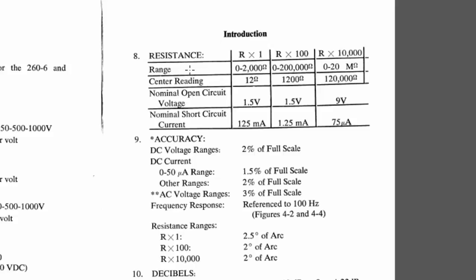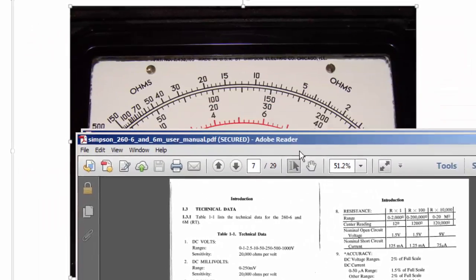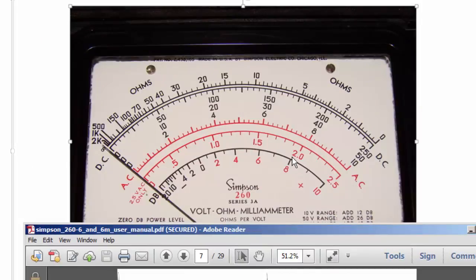So that says on the range we can read zero to two thousand ohms, the center reading is 12 ohms. So if I go back to that drawing or that picture if I look at the center scale of this meter there's 10 ohms, there's 15 ohms, each one of these marks is one ohm so right here is the center of the scale.